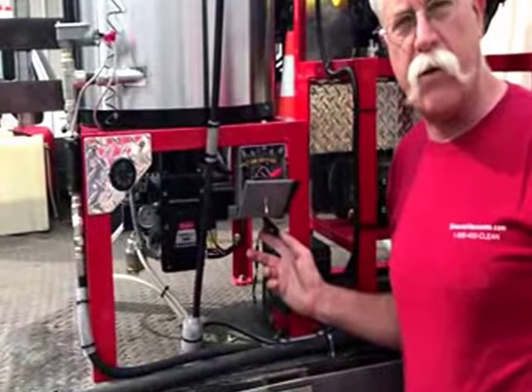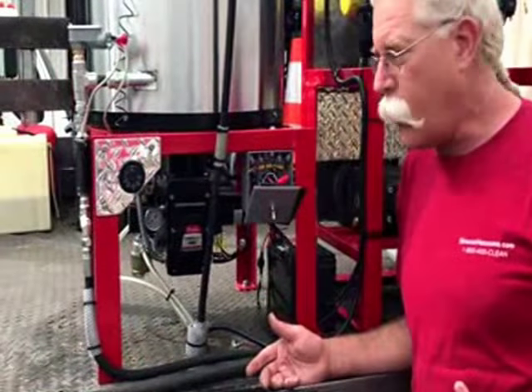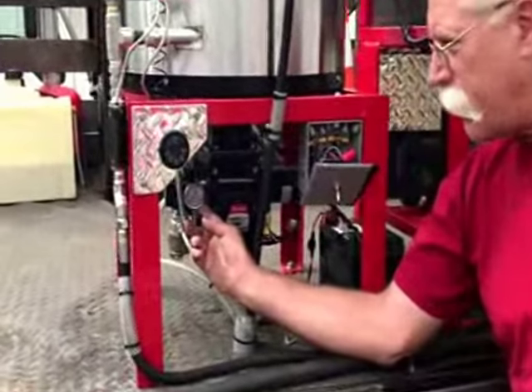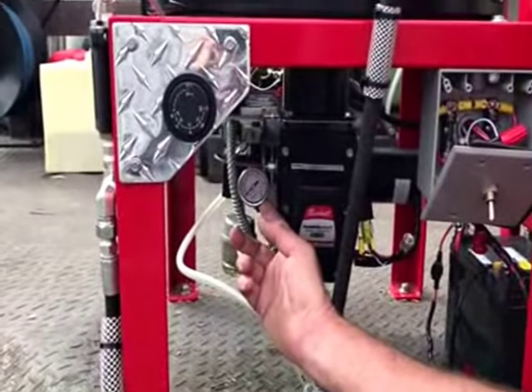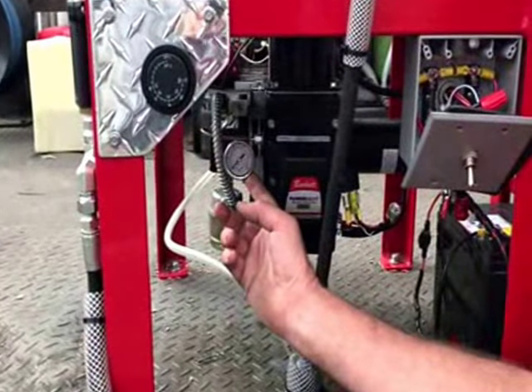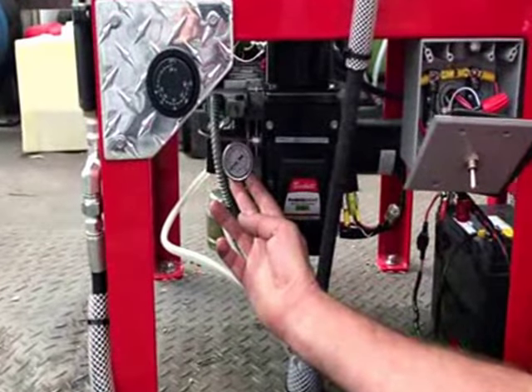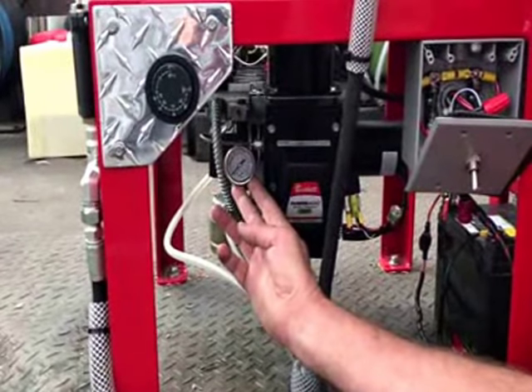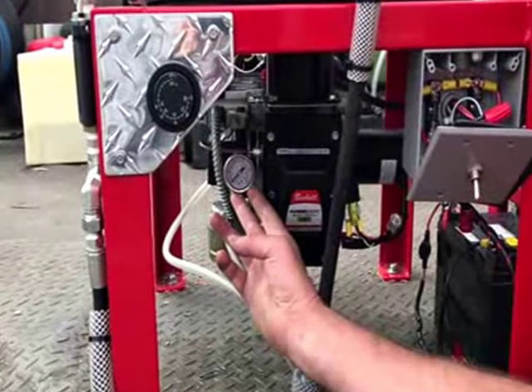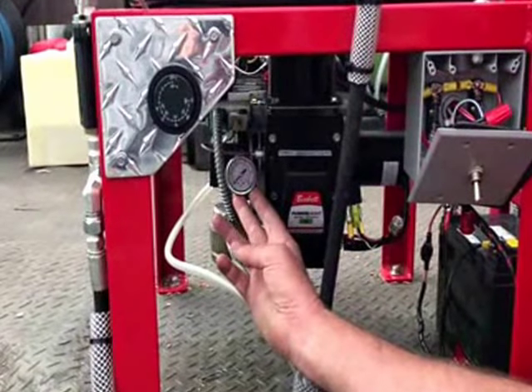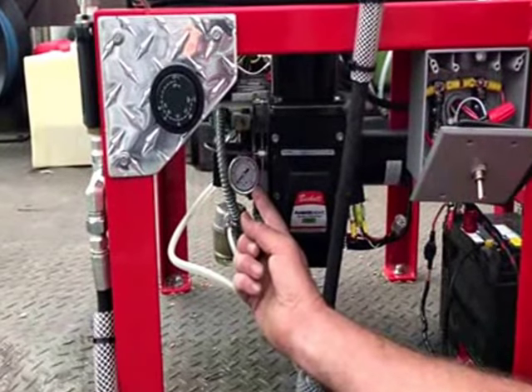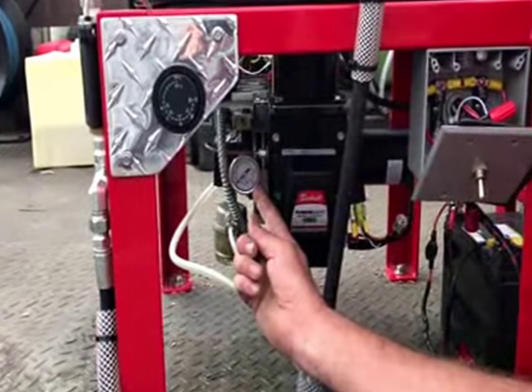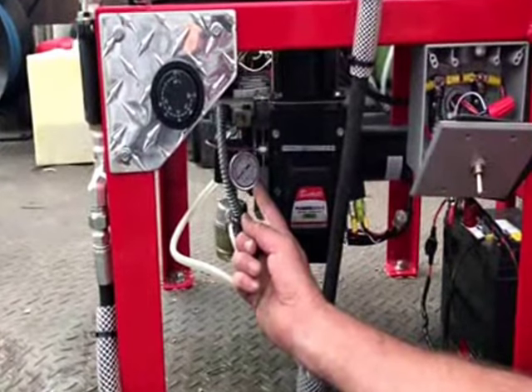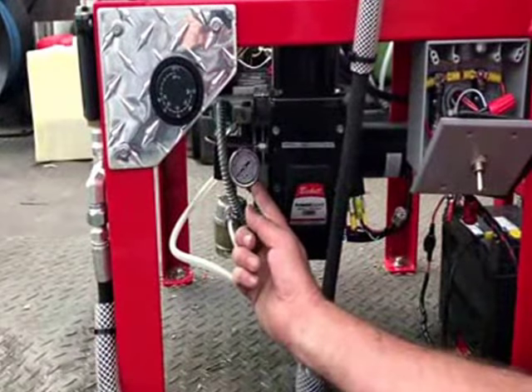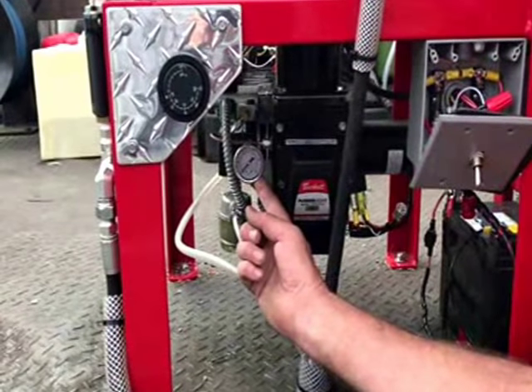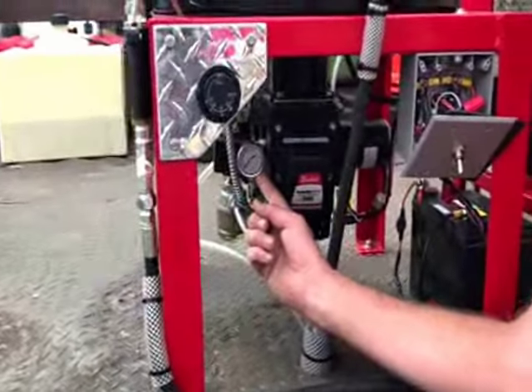These things don't live forever, so it's nice to be able to do some troubleshooting really quickly with a fuel pressure gauge on your heater. It tells us whether you've got a fuel supply, whether the pump is turning the right speed, whether it's actually pumping and making pressure. We're eliminating an hour of troubleshooting for you. Just look at the gauge and verify you've got the same fuel pressure you had before, not pegging the scale at 200 psi, and troubleshooting on that side of the system is done. You know your problem is someplace else.